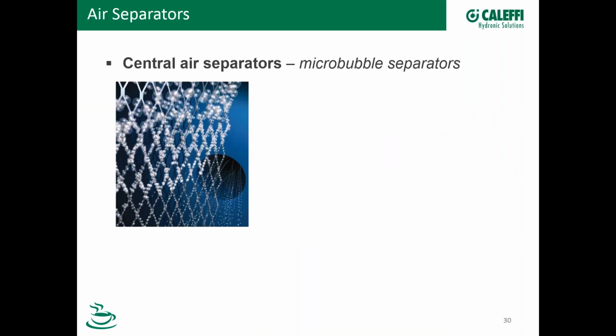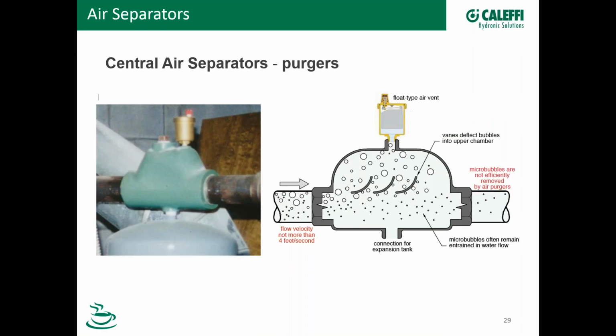Yeah, the main thing on that one, Kevin, is that the intention of that device is they make a big wide spot in the road. So as the flow comes into that, it slows down for a second as it goes through there, reducing the velocity, trying to encourage those bubbles to go up to the top and find their way out of that little, typically 1/8-inch air vent on the top. But those little microbubbles and entrained air, it just doesn't have any mechanism, that Kevin's going to explain on the next slide, to grab those and capture them and float them up and release them. So in its day, it had a place, but there's a better way to do this now, especially with high efficiency equipment, both boilers and heat emitters.